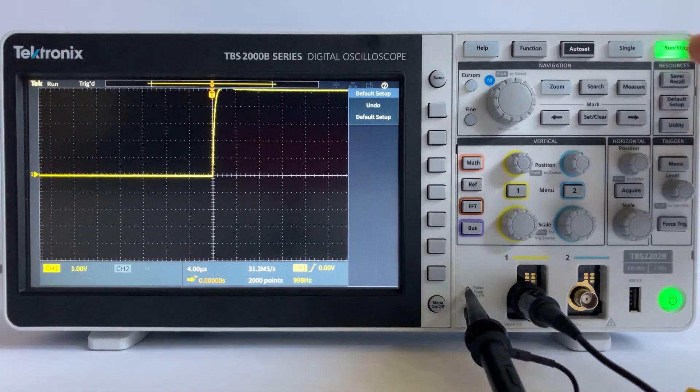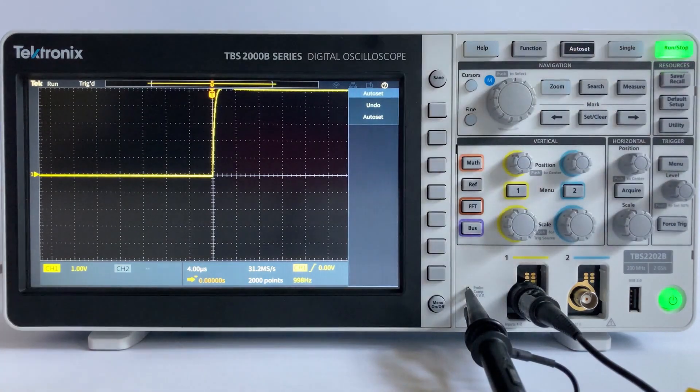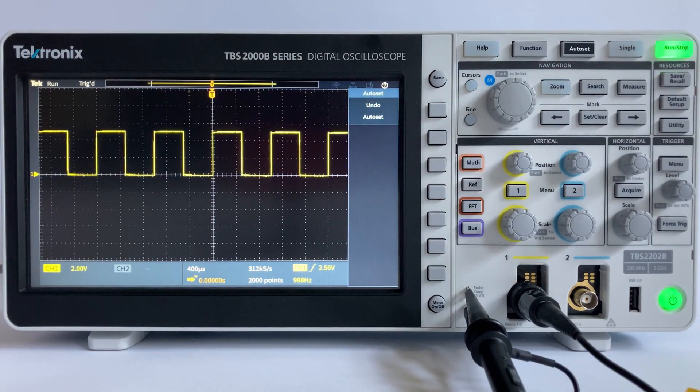As you can see, the 5V peak to peak 1kHz square waveform from the probe compensation output port is now displayed on the screen with five cycles.